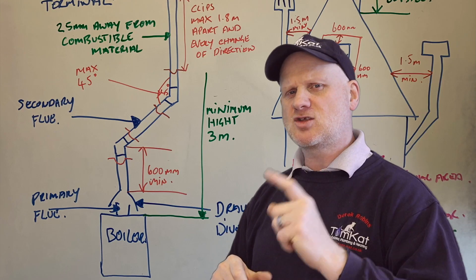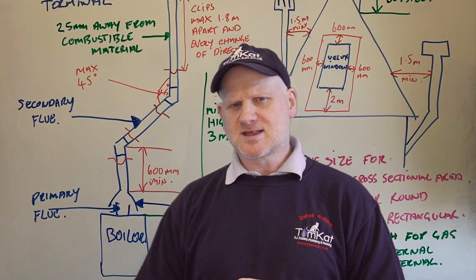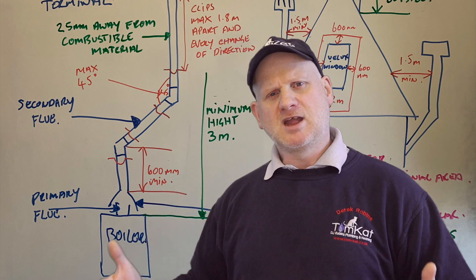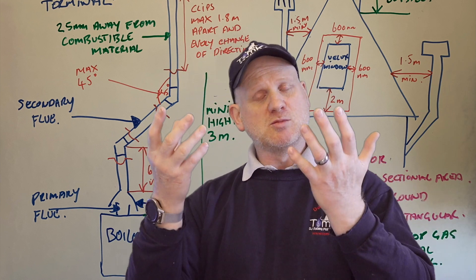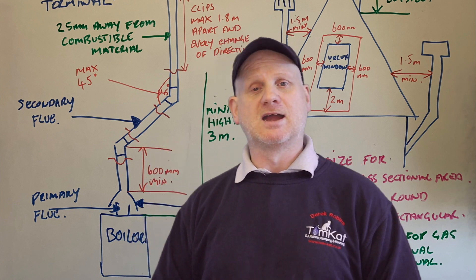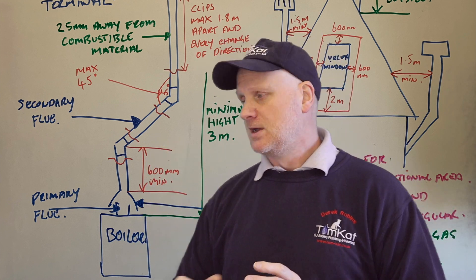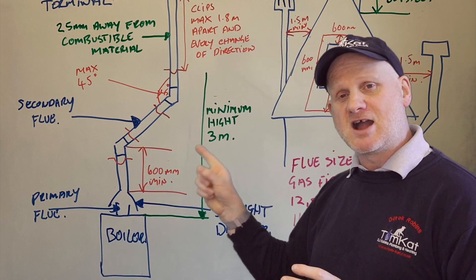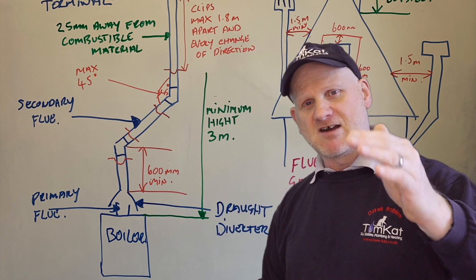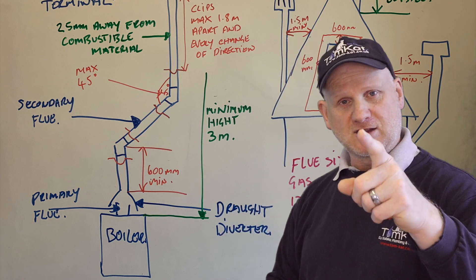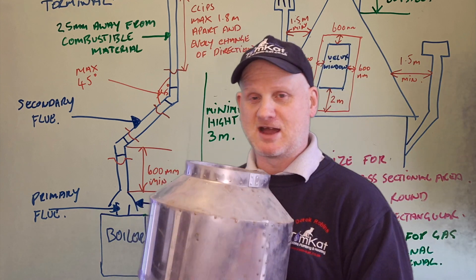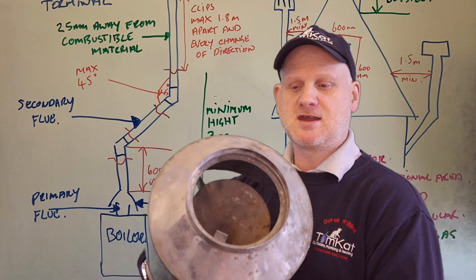Finally, the draft diverter stops excessive flue pull — if the flue is pulling too much it might lift off the burner and lift the pilot light, so it breaks that as well. The draft diverter is incredibly important and it can either be external or built into the appliance.